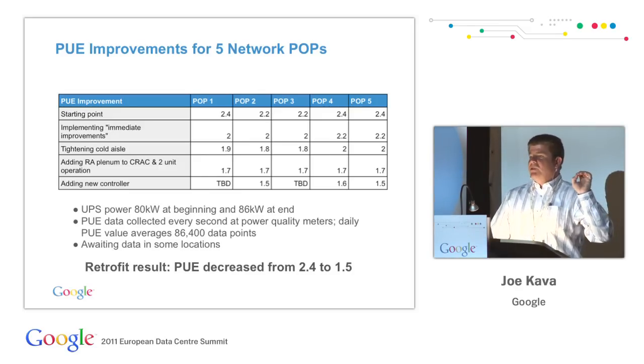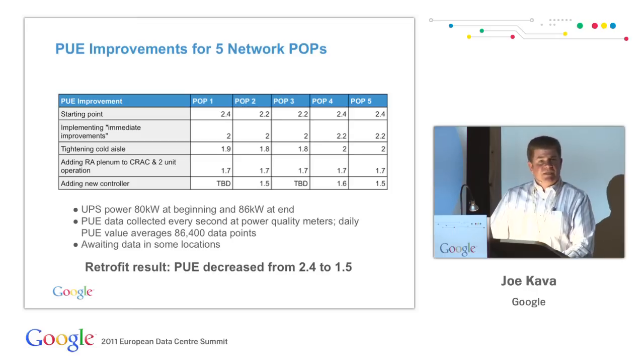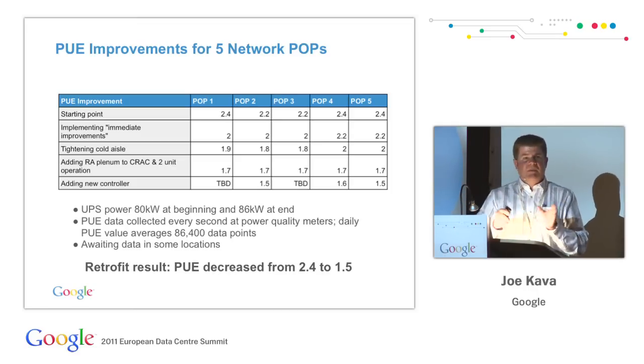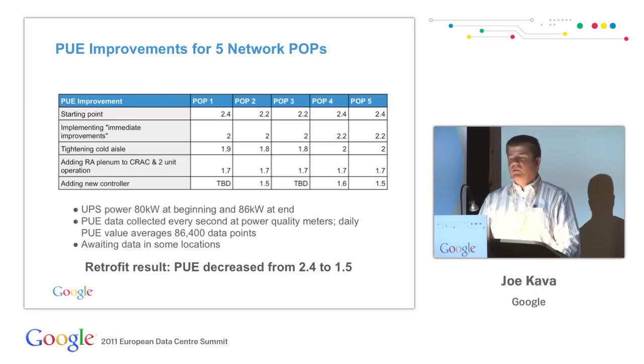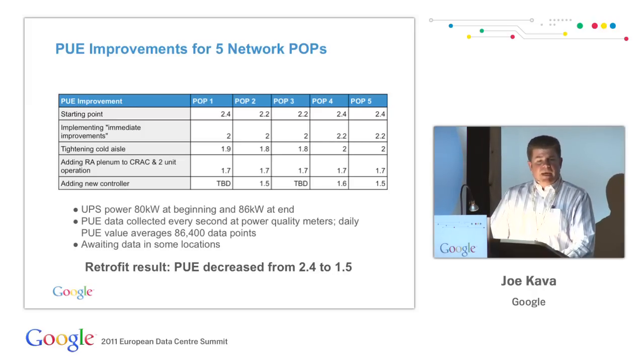At the beginning of the project, the actual utilized kW power in the room was 80 kW. At the end, it was 86 kW. So the PUE improvements were not simply because of increased IT load in the room. And overall, it represents a 0.7 to 0.9 PUE reduction, which, if you just look at the cooling overhead component, is more than a 60% reduction in the cooling overhead in these rooms.